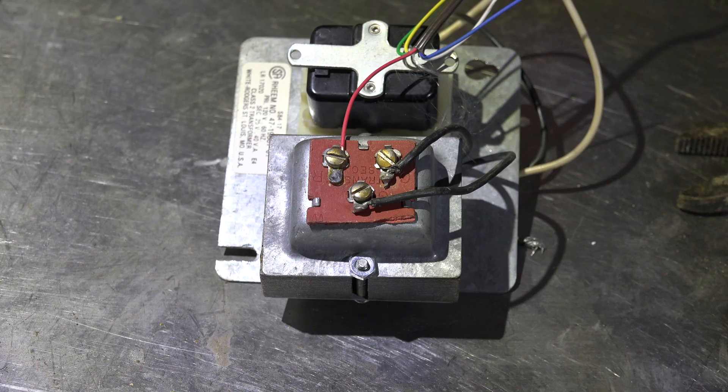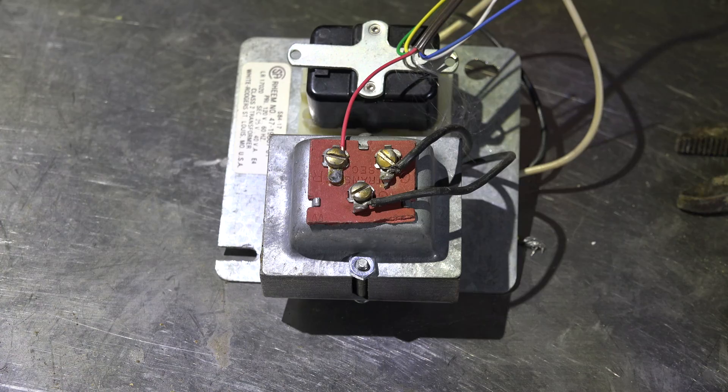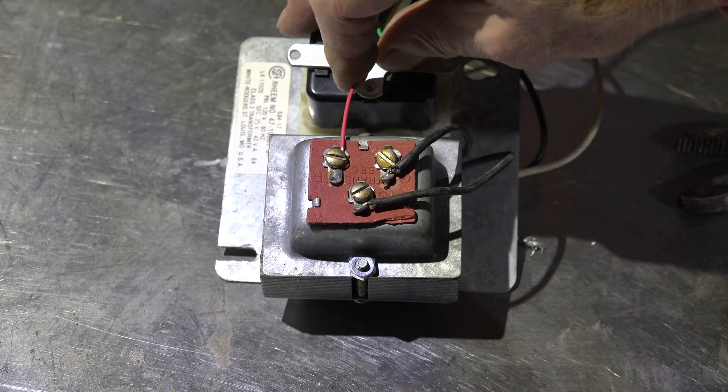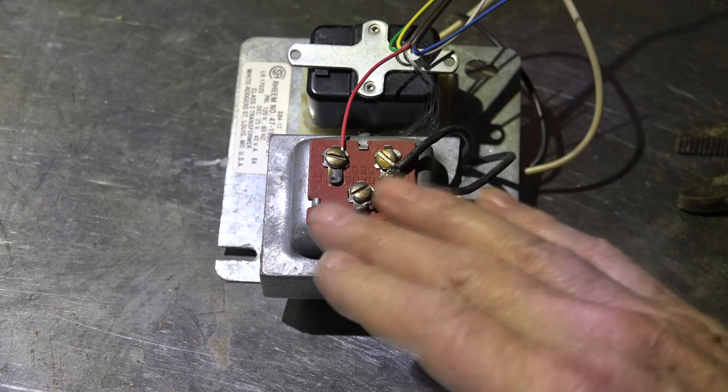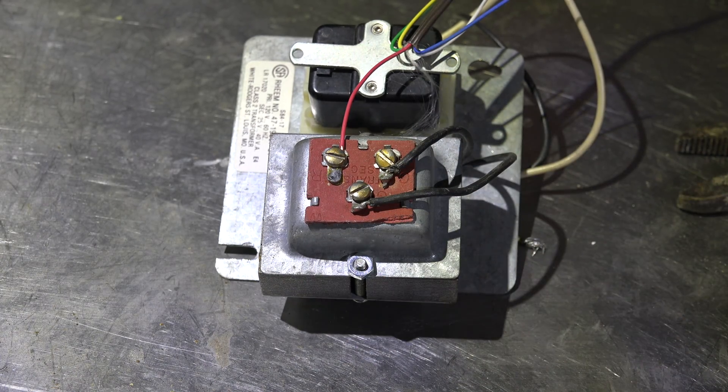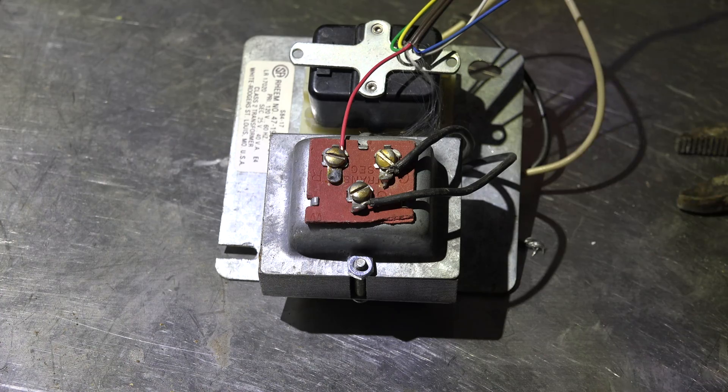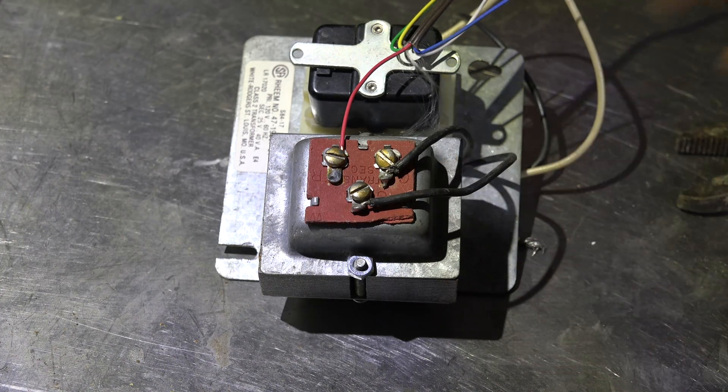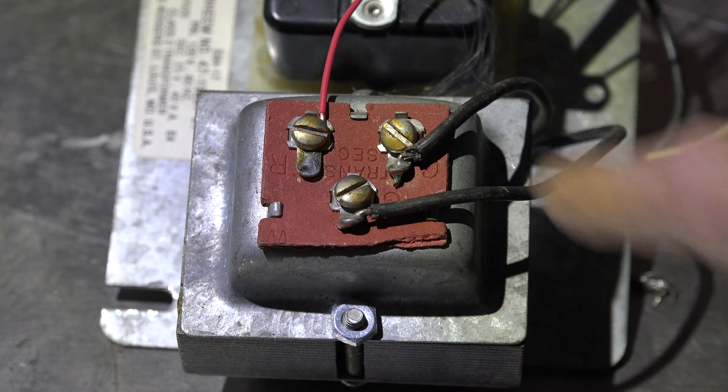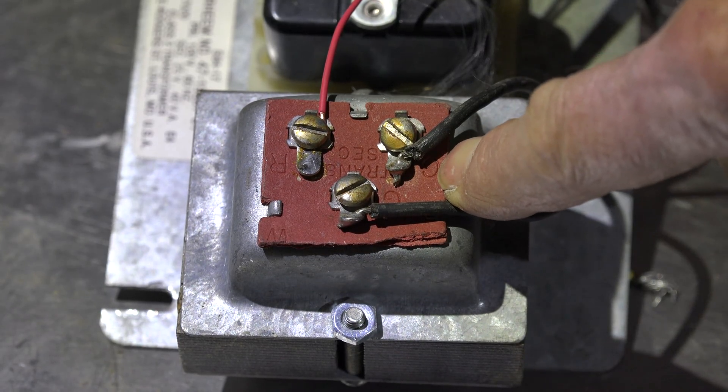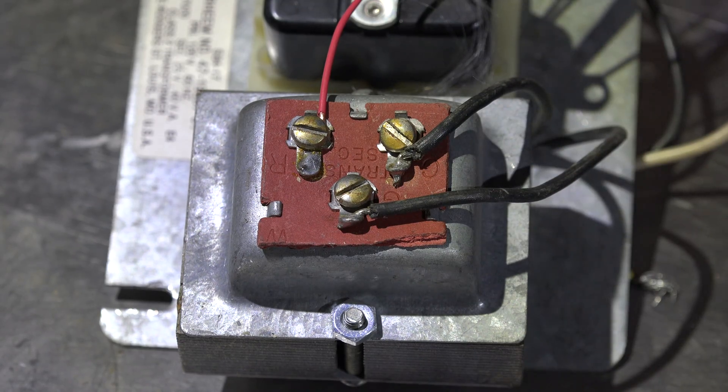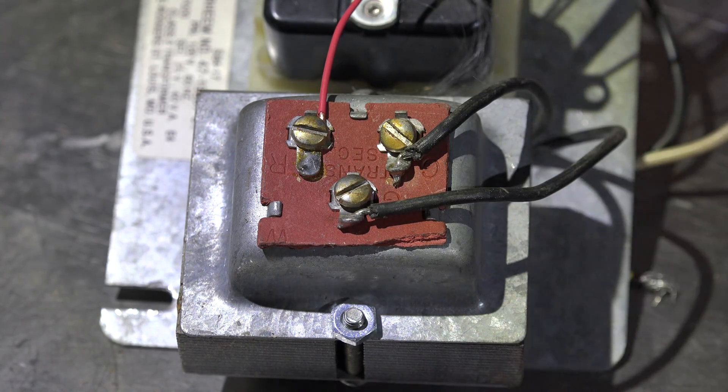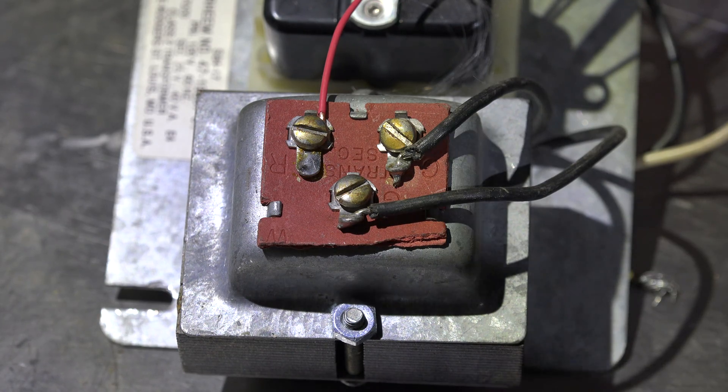Now let's look at the other one. If you have a fan center, you're also going to have a red coming off this transformer. You'll have these other wires and terminals. You can have up to five terminals there. For the most part, you can ignore those. But one of them, let's get closer, if you look close you can see that's a C for common.